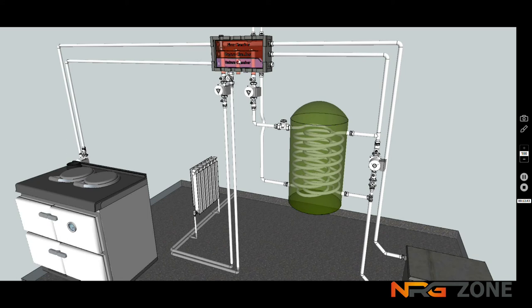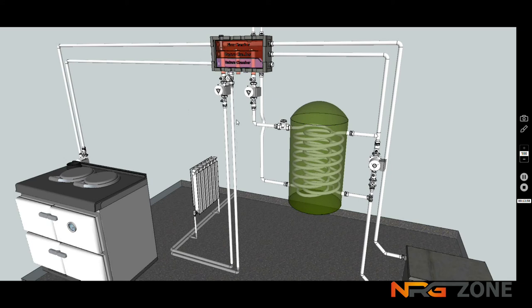The reason for the non-return valve is if this zone is not working, we don't want to take a chance of any drifted heat maybe finding its way into this path if any of those rads raise to a higher level. Because the radiator at a higher level that's heated, when it starts to cool, will cause cold water to fall down, and that in turn would cause water to rise up here, which may cause a circuit. So the non-return valve here is an insurance policy, let's say, to ensure that this zone will only work when that pump works.